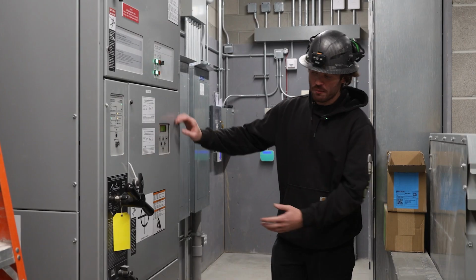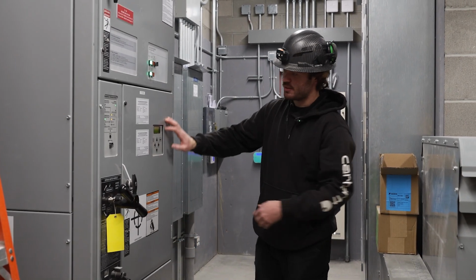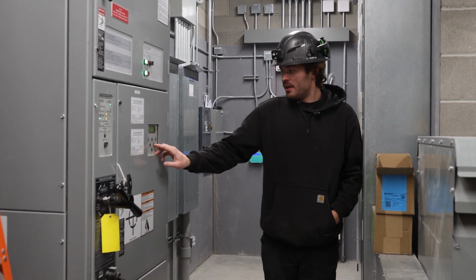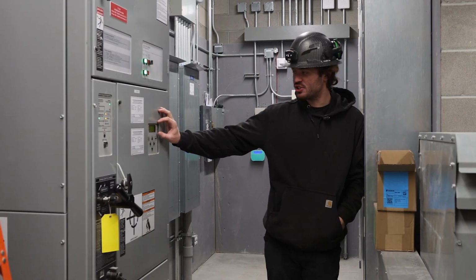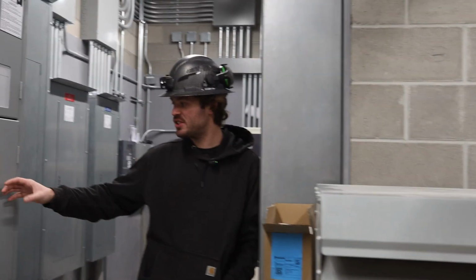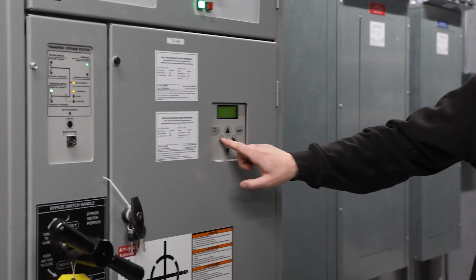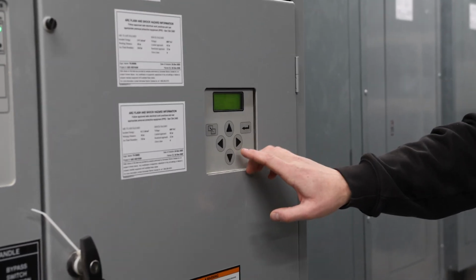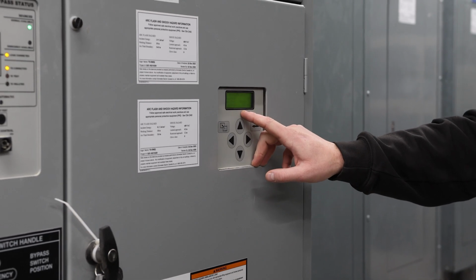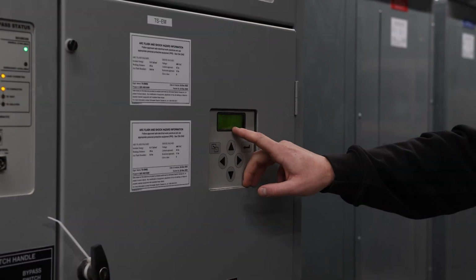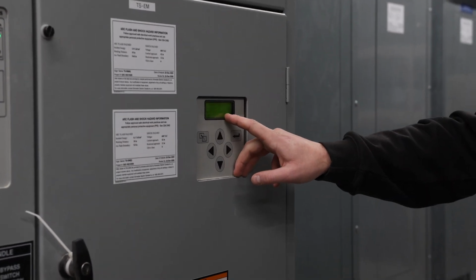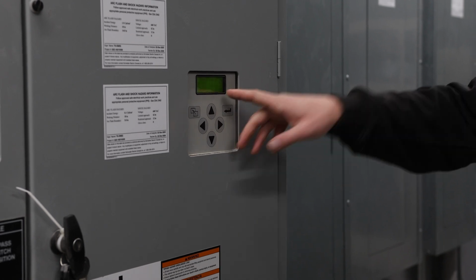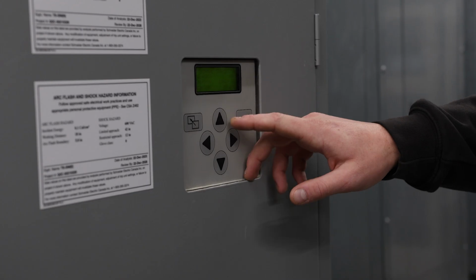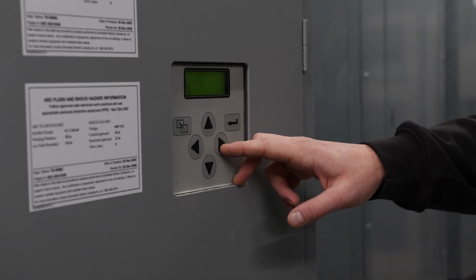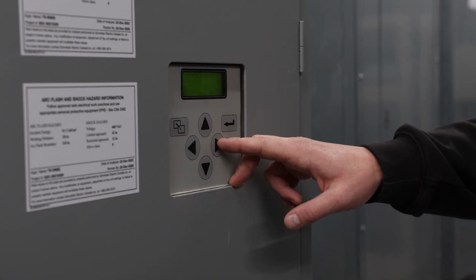To the right of our bypass and isolation crank is the main controller. This display will show you what the transfer switch is seeing, what's going on. It can be cycled through with the arrow keys. The first arrow to the right will show us our normal voltage, our current voltage, our phase rotation, and if there is a voltage unbalance, so if one leg was lower than the other two, and our frequency. It'll just sit there bouncing around showing what's going on with power to the building.